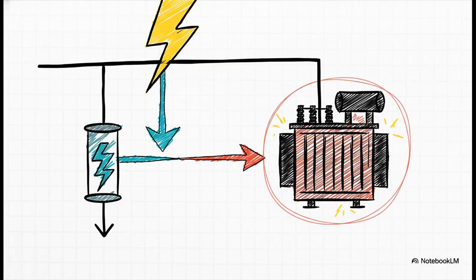And this is exactly why it matters so much. Even with the arrestor doing its job, the equipment it's protecting still feels this little zap. So the lower an arrestor can keep that residual voltage, the less stress there is on that expensive transformer sitting next to it. It is literally the difference between a close call and a catastrophic failure.